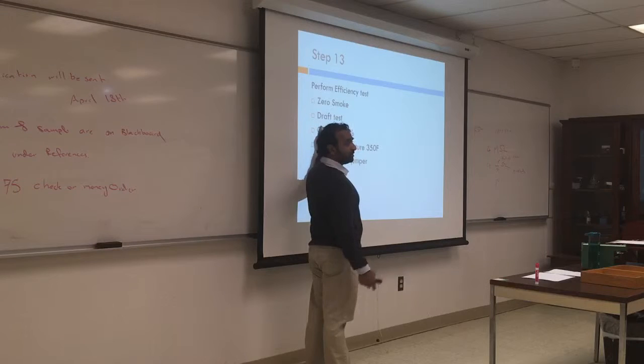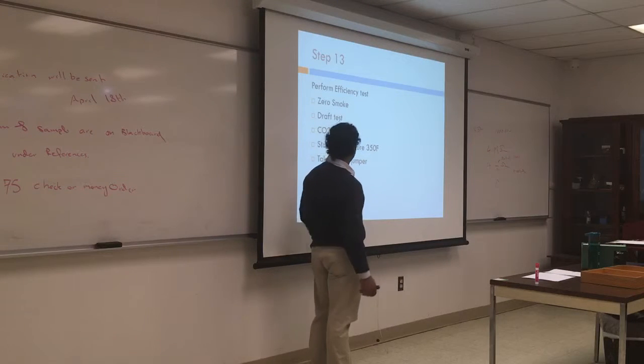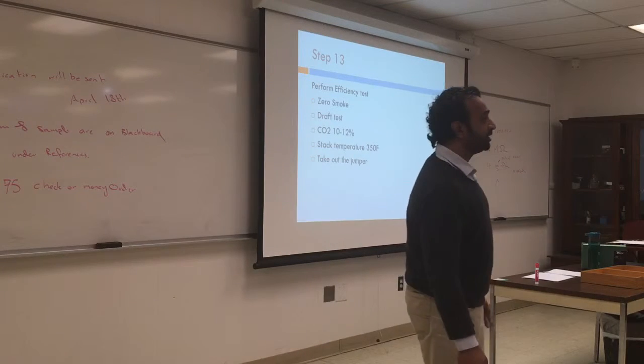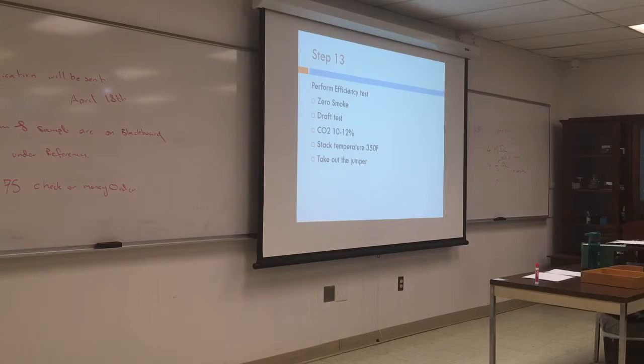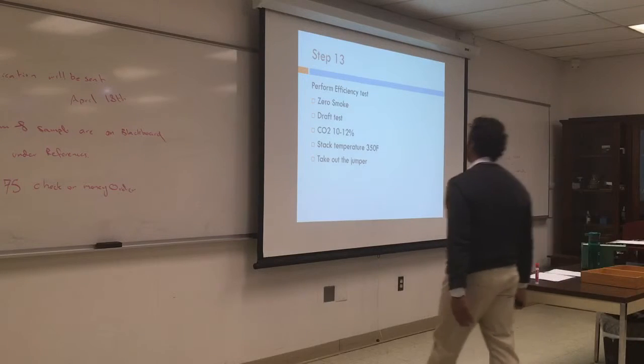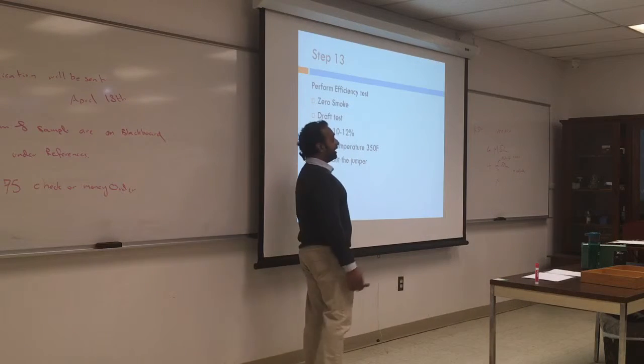We will check for zero smoke, you don't want any smoke coming out. Draft test, make sure the vent is doing the right draft, which is 0.01 to 0.02 draft. CO2 should be between 10 and 12%, and the stack temperature should be 350 net, not gross. So if it's showing you 420 and you subtract 70 for the room temperature, that will be 350. So 350 is optimal. Take out the jumper and it's almost done.